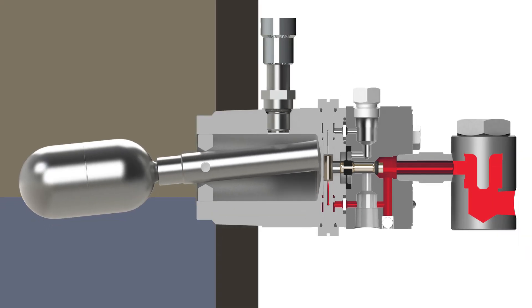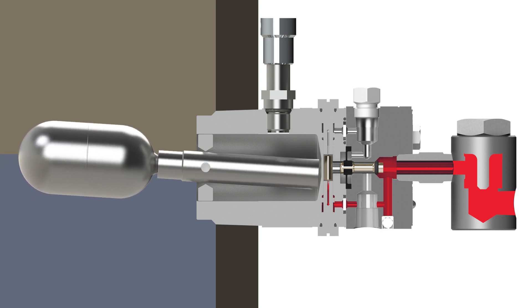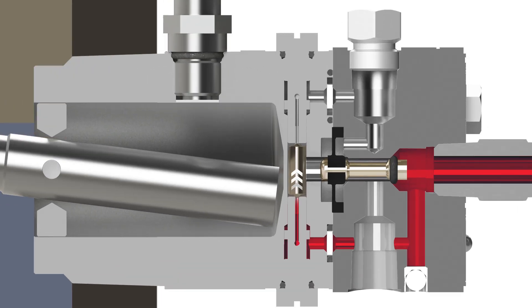As the liquid level rises and the float moves up, the float lever pivots down repelling the shuttle up. This opens the channel for the supply pressure to contact the diaphragm.